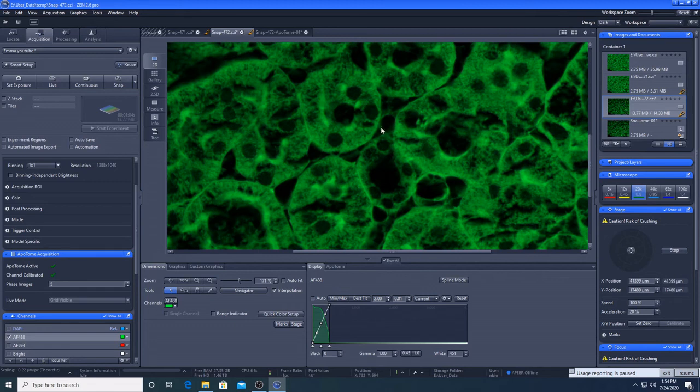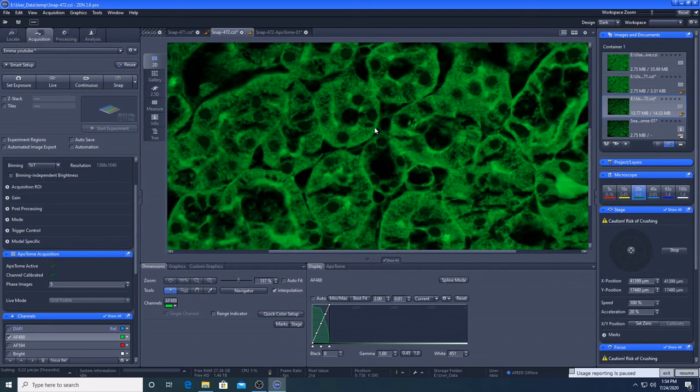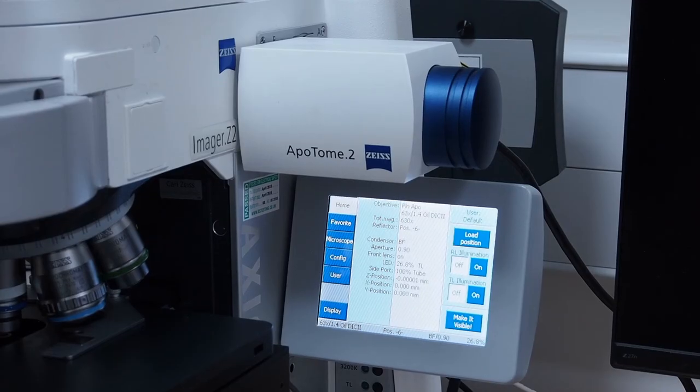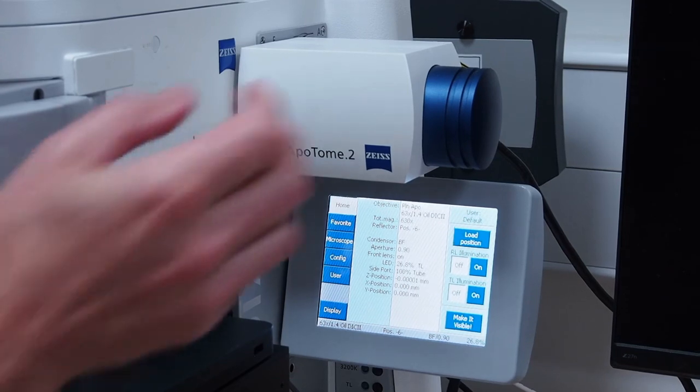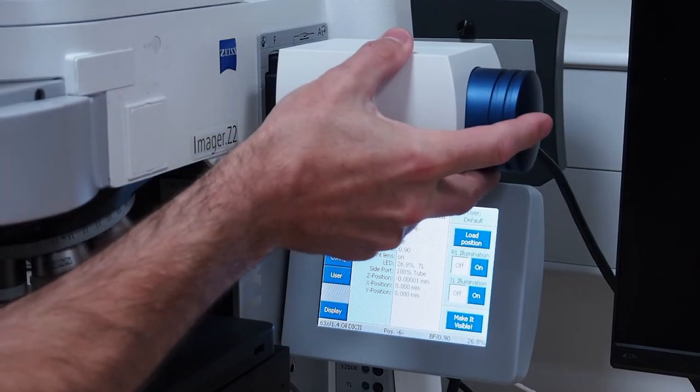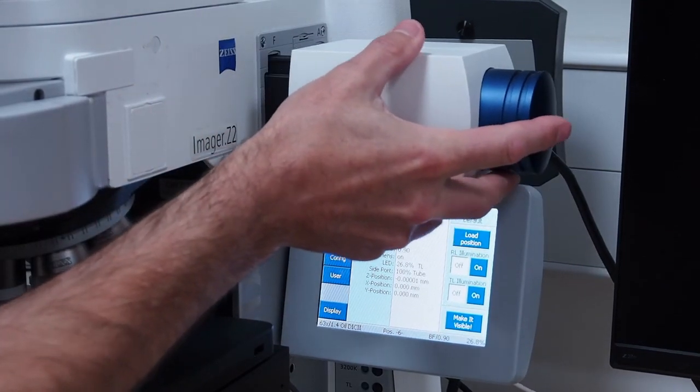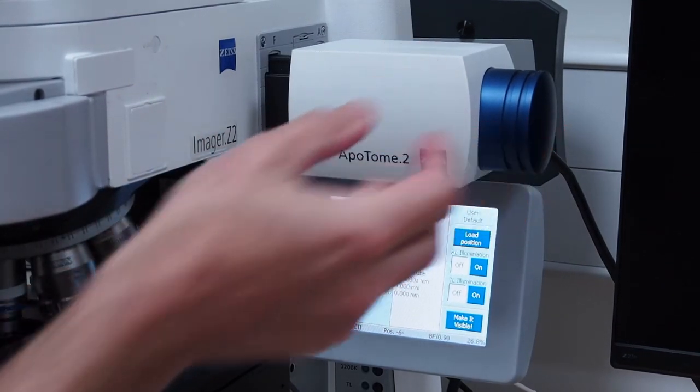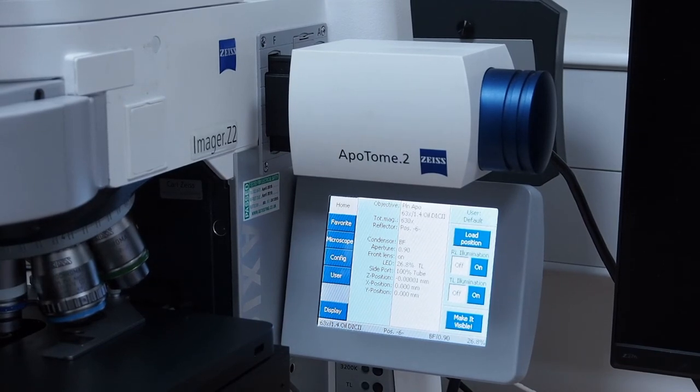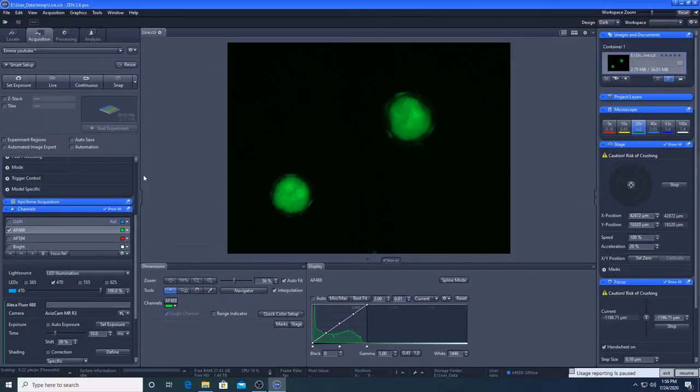So if we compare the two, this has a lot more grayscale levels. This one here has a lot more unfocused light. If I zoom in you see this haze, the green haze, that's the unfocused light. If I zoom in here it's a lot crisper. So the Apotome we would not use for measuring the amount of fluorescence but we would perhaps use it, it can be helpful for taking structural images if there's a lot of background noise and you need a fine level of detail with regards to structure. The Apotome can be helpful. To stop using the Apotome pull the Apotome slider out again until you feel it click into the outer position notch.